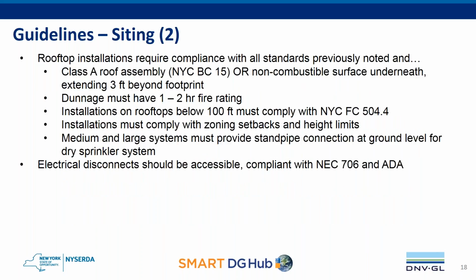Specifically for rooftop installations, as I know there's a lot of interest in rooftop installations, especially in New York City where land is at a premium, they do require compliance with all of the standards previously noted. And in addition to that, there's a requirement to have a Class A roof assembly per New York City Building Code 15, or a non-combustible surface underneath, which would extend 3 feet beyond the footprint.